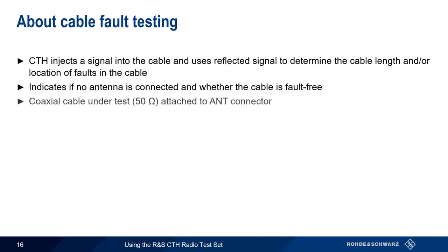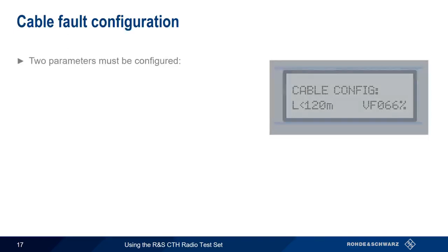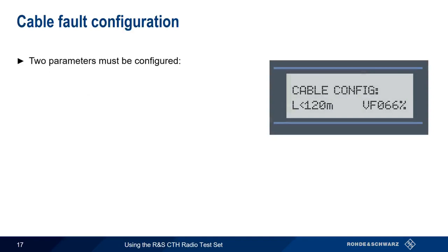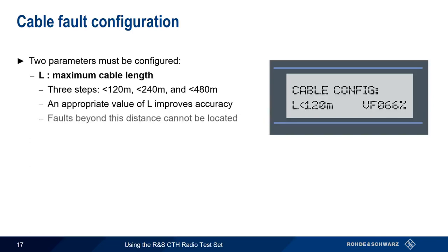To perform cable tests, the coaxial cable is connected to the CTH's antenna connector. In order to make cable fault measurements, two parameters must be configured. The first is L, the maximum length of the cable, which can be given in three steps: up to 120 meters, up to 240 meters, or up to 480 meters. Choosing the appropriate value for L improves measurement accuracy. Note also that faults beyond this configured distance cannot be located.